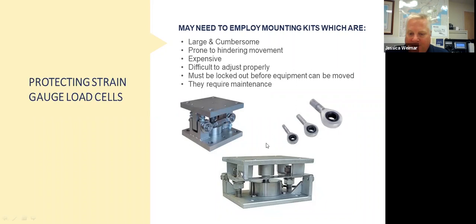But basically, this whole thing is designed so that the load that the cell sees is in a fully vertical direction. Any kind of a side load in this particular installation would get picked up by these turnbuckles that you see right here. Any kind of an overload would get picked up by these travel stops that you're seeing right here. These are adjustable, as you see. This one also has liftoff protection that you'll see here so that the vessel can't come off the top of the unit. But again, this whole system is designed to protect that load cell from seeing loads in a direction that it can't tolerate.